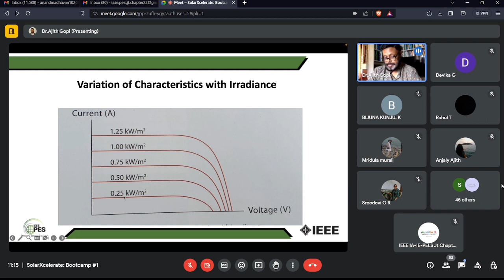If you have STC and NOCT, STC is nothing but the standard test conditions. NOCT is nominal operating cell temperature. You have ambient temperature 20 degrees centigrade, irradiance 800 watt per meter square, and wind speed 1 meter per second. All Europeans put these standards, not our standard. So cell temperature is 25 degrees centigrade, air mass 1.5.